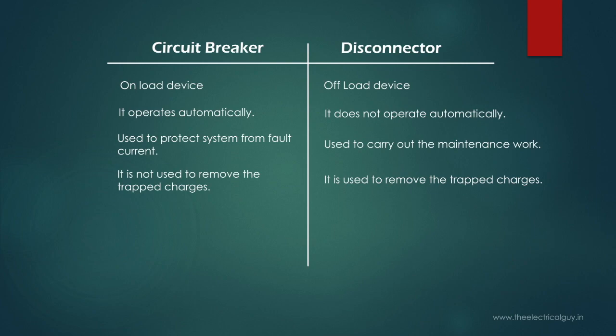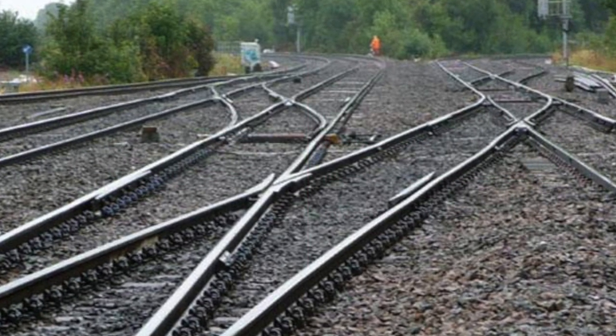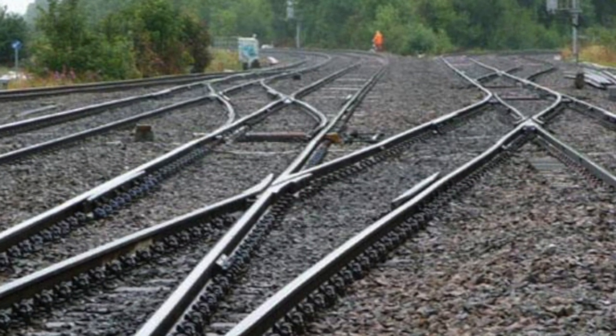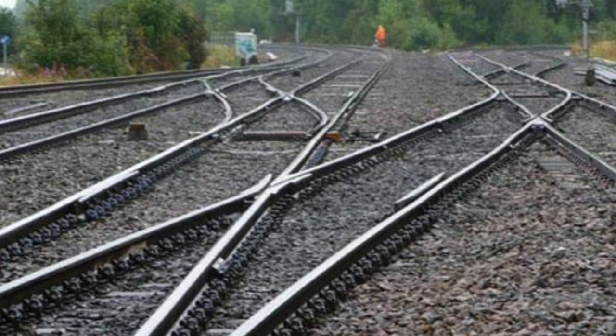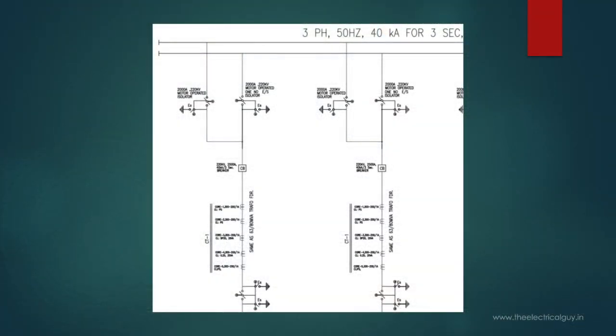Next important application which most people forget to tell is to reroute the power flow. For this application, disconnector works exactly same as the railway tracks, which helps the railway to change its route or lane. In most of the substations, two buses are provided. One is main bus and another is auxiliary bus.